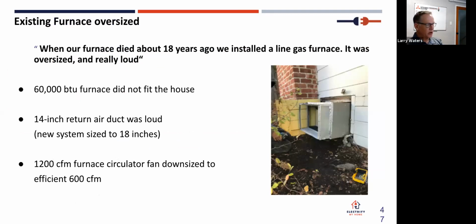This furnace was so big, 60,000 BTUs. If I were to put a 60,000 BTU heat pump in, it would be in a 26 or 2800 square foot house. This is a ridiculously oversized furnace. It had a 14 inch return air, meaning the air going into the furnace was funneled through a small space with a lot of air moving through it. It made all kinds of noise—it was really, really loud. It was 1200 cubic feet per minute of air moving through this 1000 square foot house.